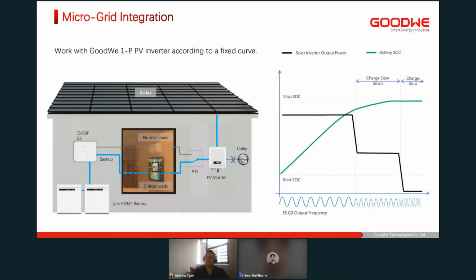So if you have another brand grid side inverter, it's not a problem. The control is done through grid frequency, not through RS485 or Wi-Fi or something else, which might require the same brand on both products.